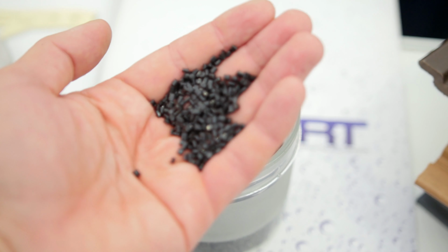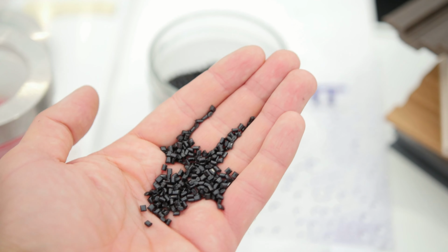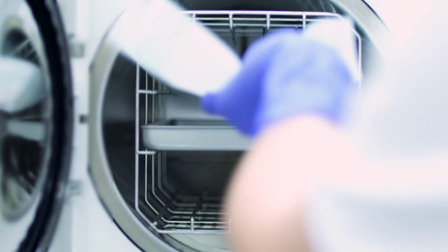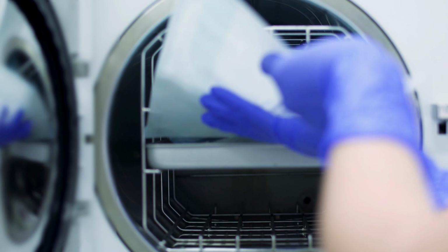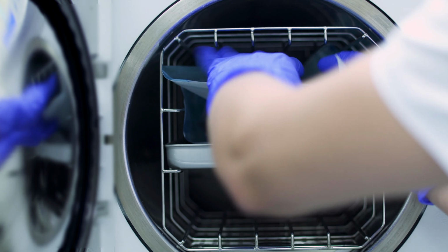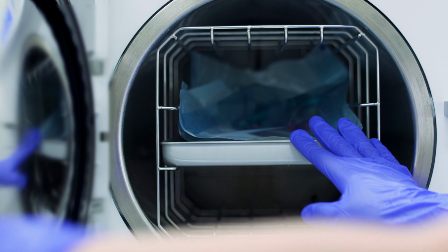And a lot of times these have biocompatible or in-human use pedigrees that are different from those you find in consumer products. We need to ensure that the material that we've selected for our product meets the ISO standard 10993, can withstand up to multiple sterilization rounds in gamma, ETO, or steam sterilization, and that we have the proper documentation to support the claims that we're making.